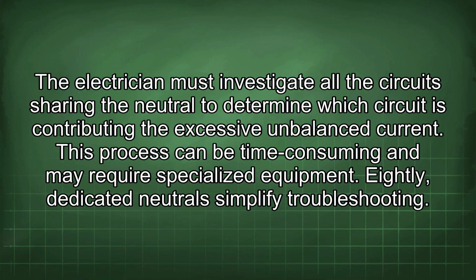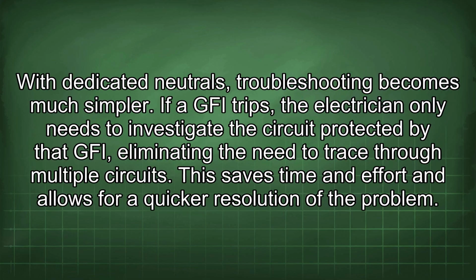8. Dedicated neutrals simplify troubleshooting. With dedicated neutrals, troubleshooting becomes much simpler. If a GFI trips, the electrician only needs to investigate the circuit protected by that GFI, eliminating the need to trace through multiple circuits. This saves time and effort and allows for a quicker resolution of the problem.